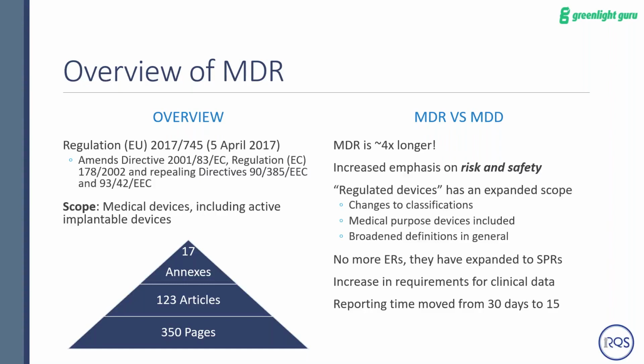There are also some changes to the scope. Previously, for CE mark, certain devices that didn't have a medicinal application were not considered medical devices. Certain accessories were not considered medical devices. A lot of that's changing. So a lot of previously unclassified devices are now going to fall under the scope of the MDR. So that's a big change.